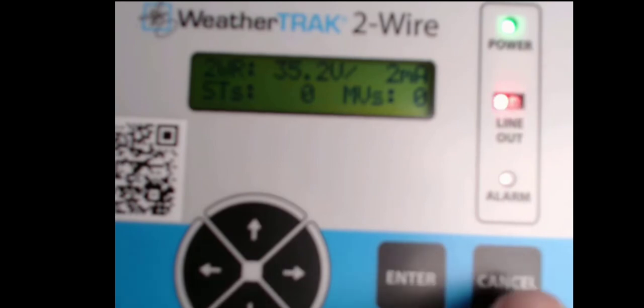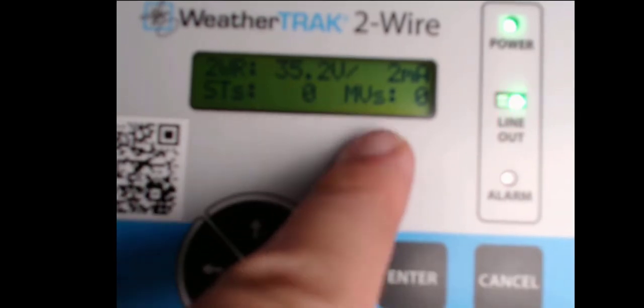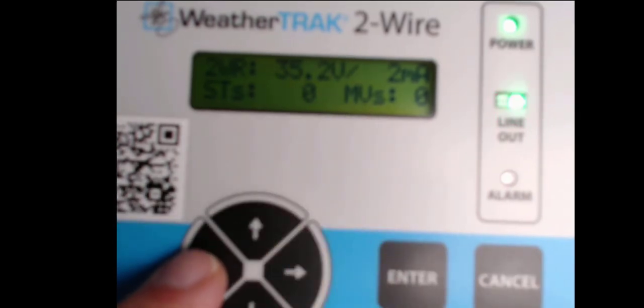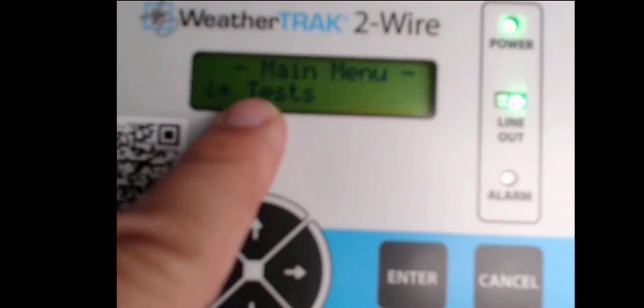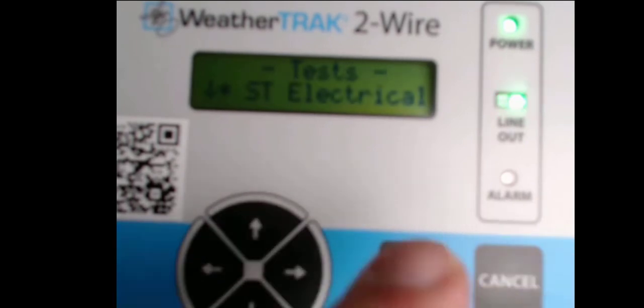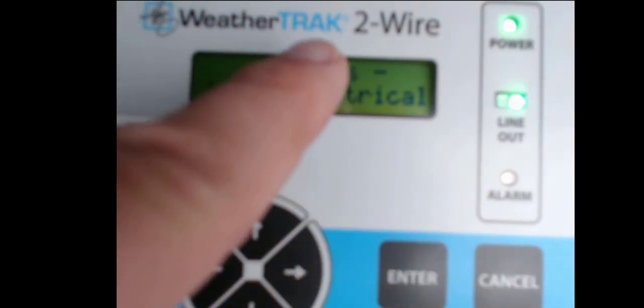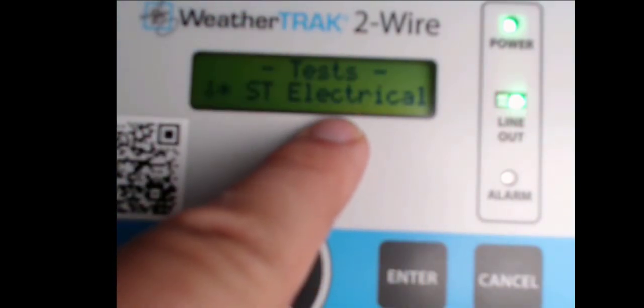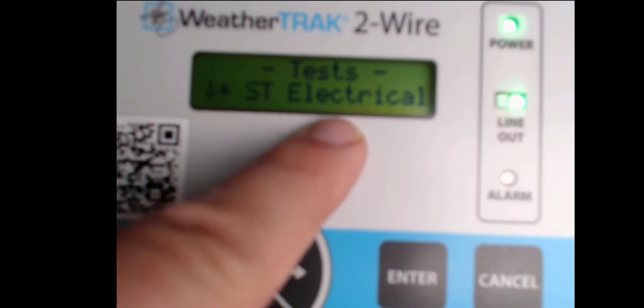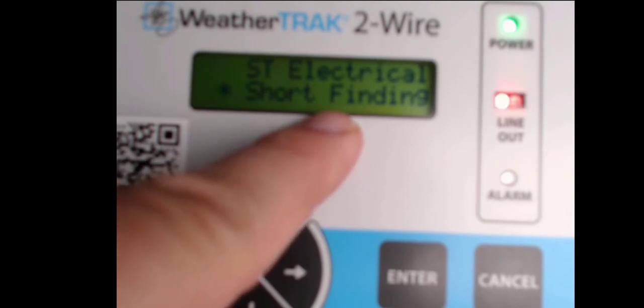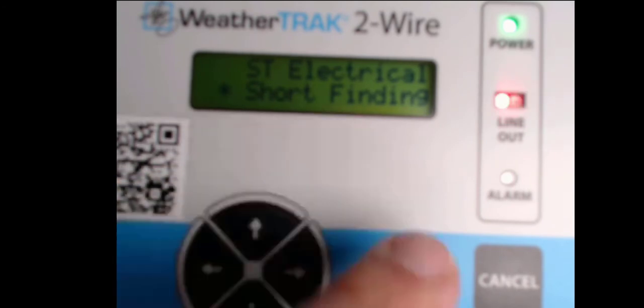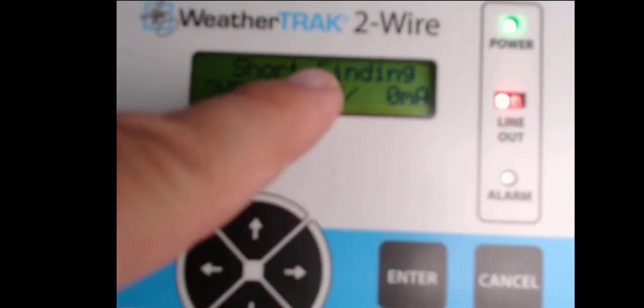Hit enter on Tests. The first option is 'Station Electrical,' which is not the test we want. Scroll down one option to 'Short Finding' and hit enter. That will turn on the short finding mode on the controller. When you turn on the short finding tool, the controller sends a diagnostic signal down that wire that can be measured with a leaking current clamp meter. Before going further, we need to talk about the two tools required for WeatherTRAK 2-Wire troubleshooting: specifically a site map showing the run of the 2-Wire path, and a leaking current clamp meter.